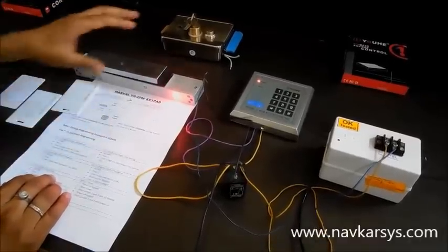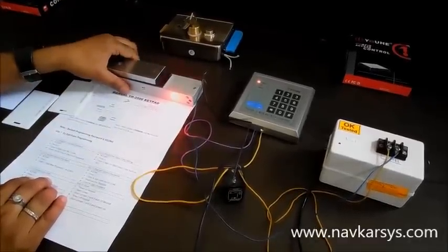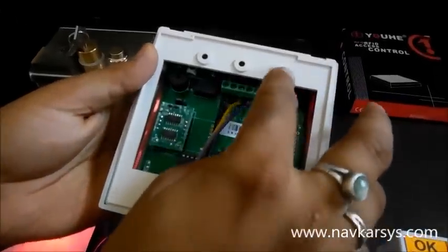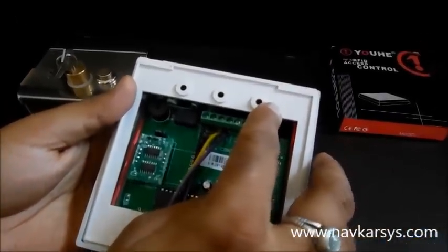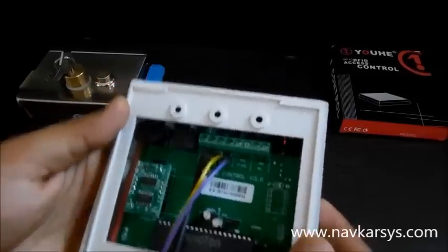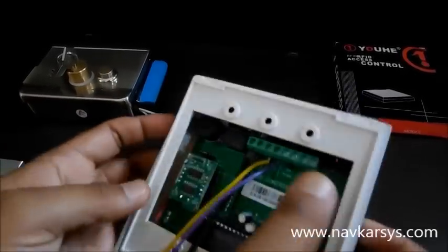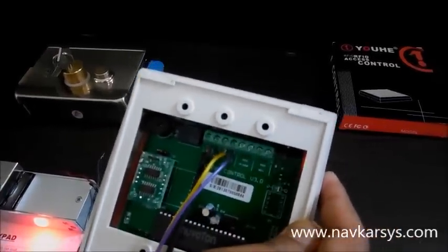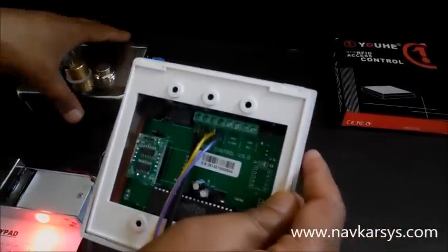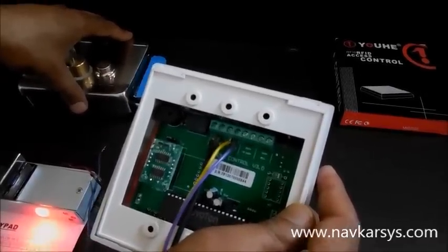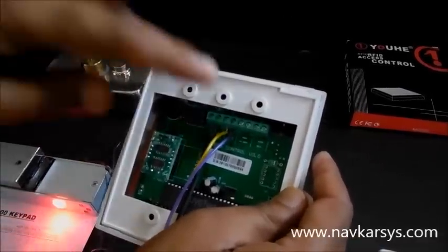When using the electromagnetic lock, the jumper settings should be configured as follows: there is an NO NC jumper on the back side, on the above side. It should be set with the common and NO when using the electromagnetic lock. So NO and common should be shorted. When using the electronic lock, NC and common should be shorted with the jumper. This is the setting for the jumper.